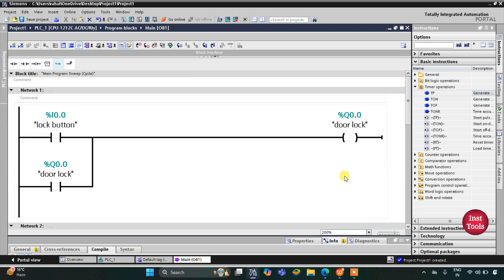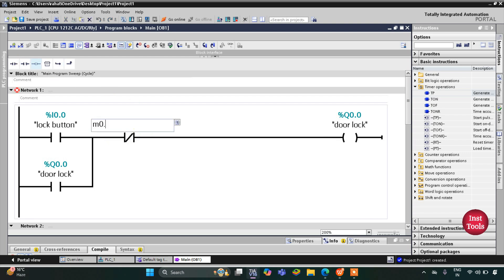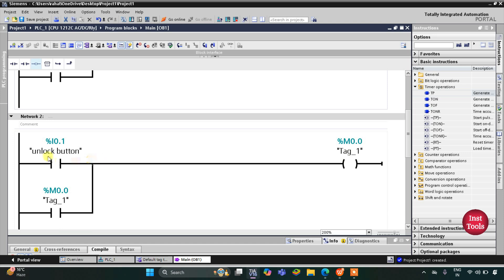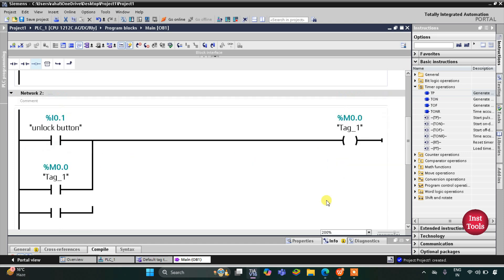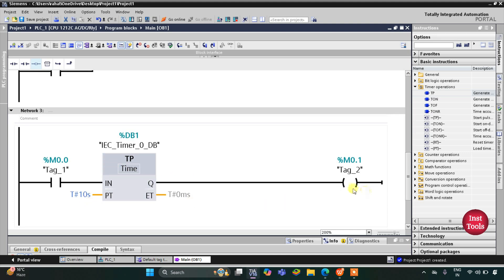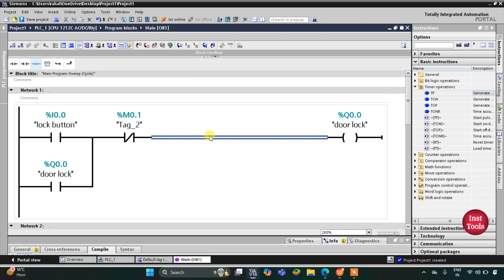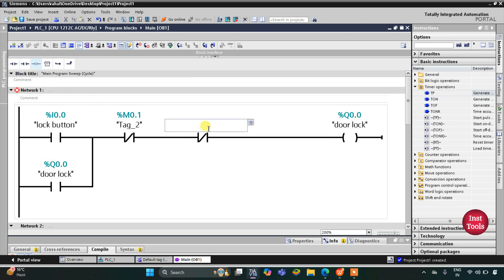Then M0.1 will be used as a normally closed contact in the door lock rung. When the lock button is pressed and released, door lock gets on. When unlock button is pressed and released, M0.0 gets set, and when M0.0 gets set, M0.1 gets set for 10 seconds. While M0.1 is on, the door does not get locked — it remains unlocked for 10 seconds. Additionally, there will be a sensor to detect presence at the door; if the sensor is activated, the door does not get locked.